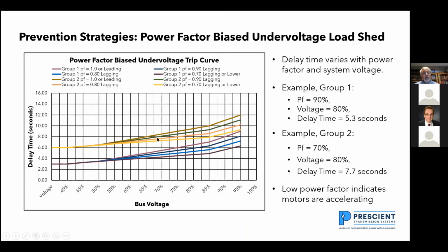I'm showing 2 characteristics here, a group 1 and a group 2. And this is just showing that if I change the time delay, this is a nominal time delay of 3 seconds. If I want to change the time delay to 6 seconds, what I do is I change the position of all my curves. So this was the 70% power factor curve starting with a 3-second delay. And this is the 70% power factor curve starting with a 6-second delay.